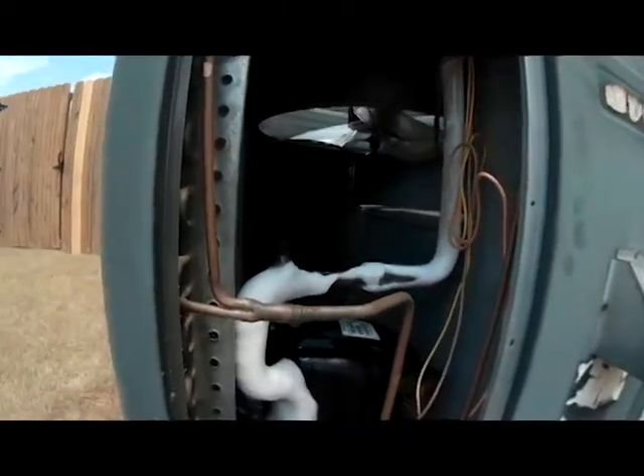I know it's not the blower motor because I felt air coming out of my vent — so just by feeling the air, we know the blower motor's working, and we don't have to take that panel apart. When you have all this ice and the evaporator coil is completely iced up, I'm going to have to take a water hose and spray down all the ice off the lines. I'll have to open up the evaporator coil and completely thaw that out. I'll check the filter too and let you know if it's stopped up.